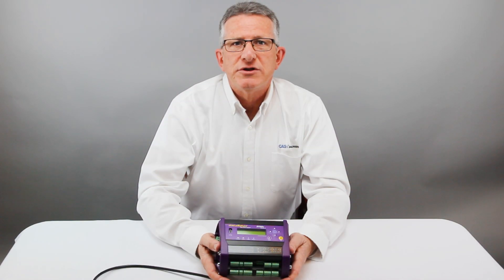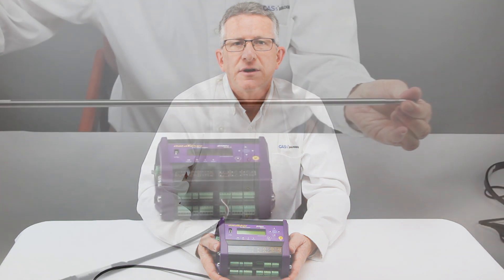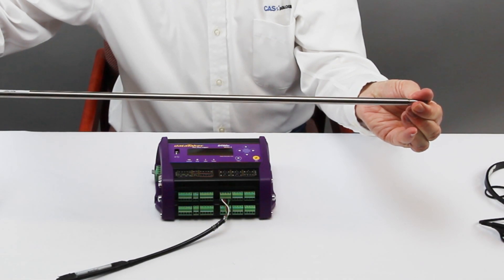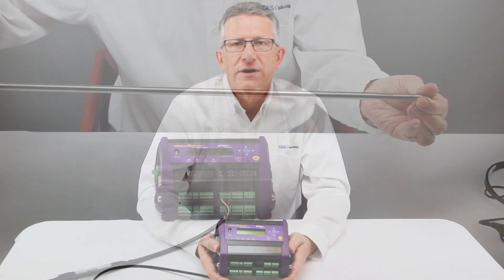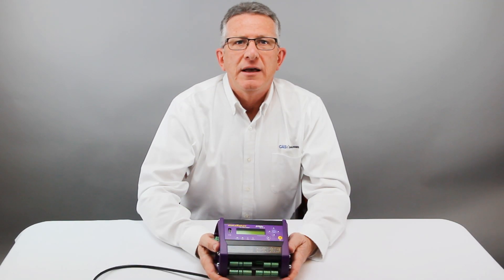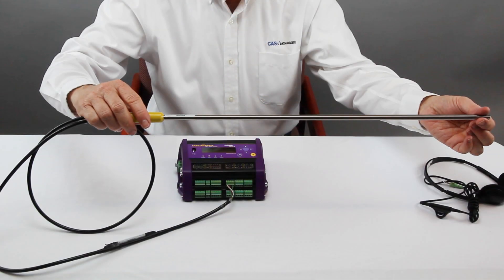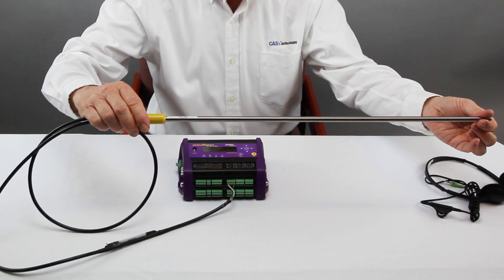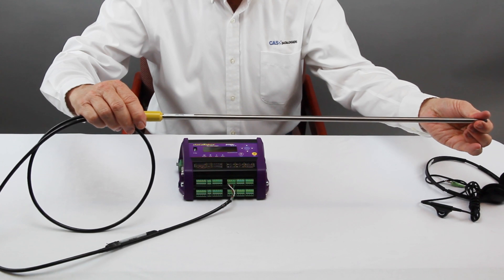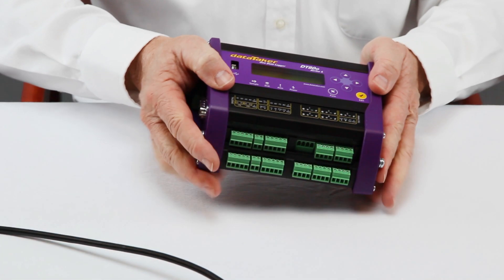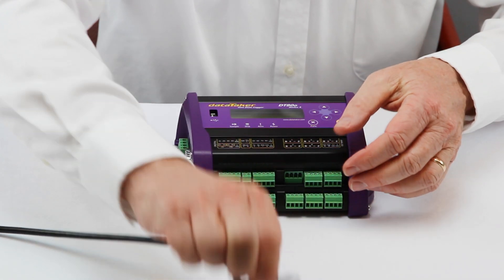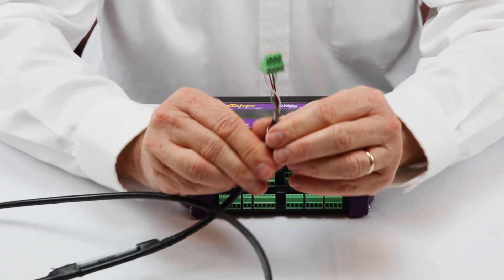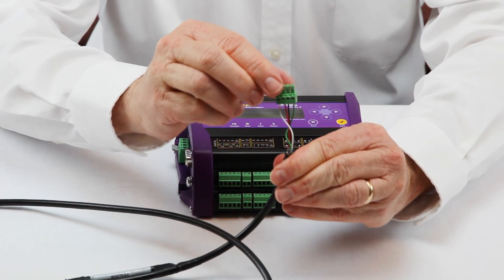For this demonstration, we are using a Roctest JMT displacement sensor that is commonly used to measure movement at joints or cracks in structures and foundations. It consists of a vibrating wire sensor attached to a tension spring with anchors at each end. There is also an embedded thermistor sensor to measure temperature. The sensor has four wires: red and black for the vibrating wire sensor and white and green for the thermistor.